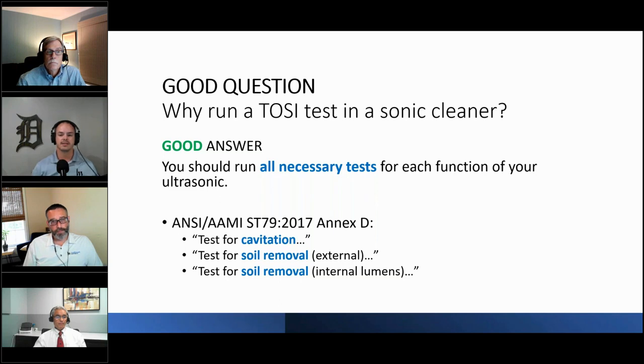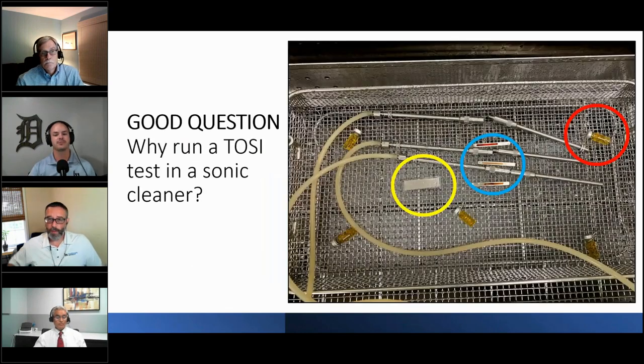your ultrasonic. Some ultrasonics actually perform thermal disinfection. So in all honesty, if you're running your ultrasonic cleaner to also thermally disinfect, you probably should be checking the temperature of that ultrasonic bath water as well.